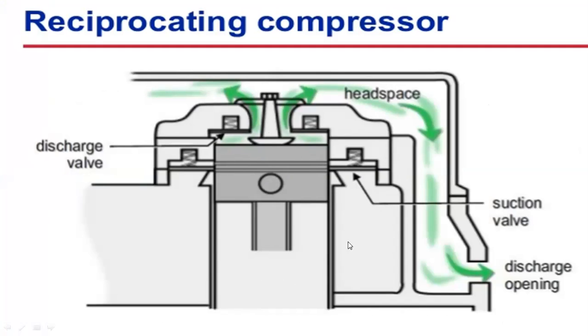Around the circumference, we have the suction valve, and on top we have the discharge valve. As the piston comes down, it sucks the air or fluid inside. And as the piston goes up, it compresses and then sends the fluid out through the discharge opening. This is the typical functioning of a reciprocating compressor — as the piston continuously moves up and down with the speed of the engine, it is sucking the air, compressing it, and discharging it.